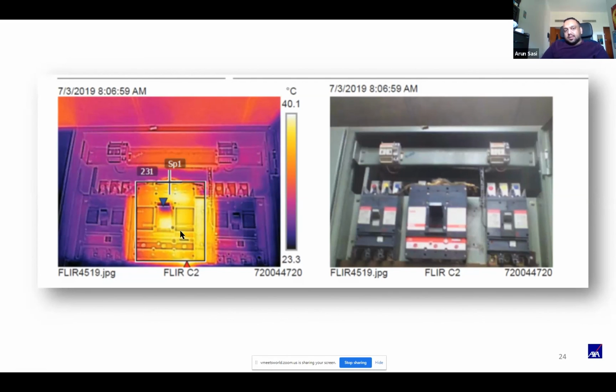It wasn't bad enough to cause a short circuit, but this is a fire waiting to happen, and the client wouldn't know about it until they had done either a daily inspection or an inspection using a thermal imaging camera.